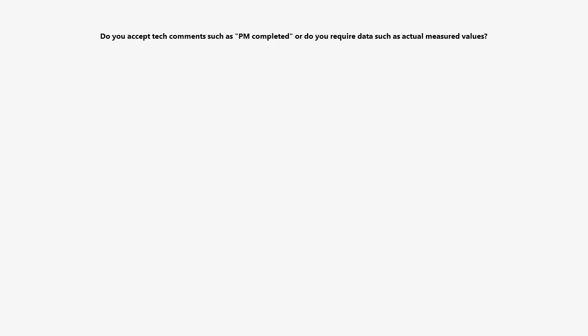Do you accept tech comments such as 'PM completed,' or do you require data such as actual measured values? In our facility, we do exception reporting. So if I say PM completed, I've got to back that up with full documentation of what the PM was, whether that's the service manual if you're following that, or your own written preventive maintenance procedures with detailed documentation. If I say I passed, and anybody asks what I did to pass, here it is, boom, this is all the stuff I did and it passed. Exception reporting is for anything that didn't pass. I do a PM with issue and detail exactly what did not pass and what we did to verify and correct it to make it pass.